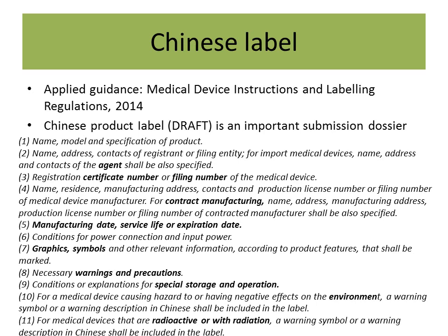The cited regulation for Chinese label is the same as for Chinese IFU. The critical items are certification number, validity or expiration date of medical device. If the size of Chinese label is limited, at least the product name, model, specification, production date and expiration date or expiry date shall be marked, and, for other details, please refer to the instruction manual, shall be clearly stated on the label. It seems that Chinese labeling is not that complex so far.